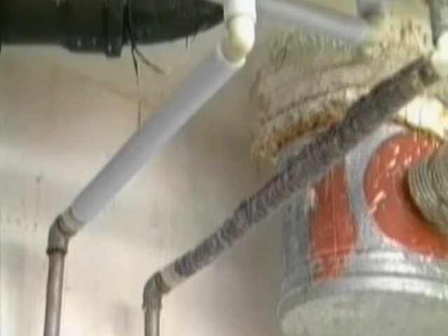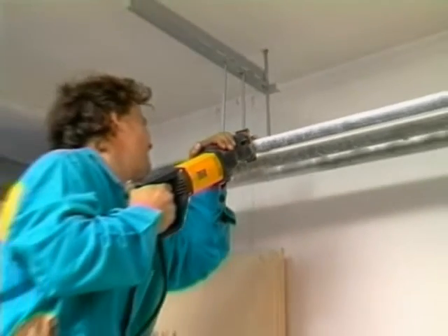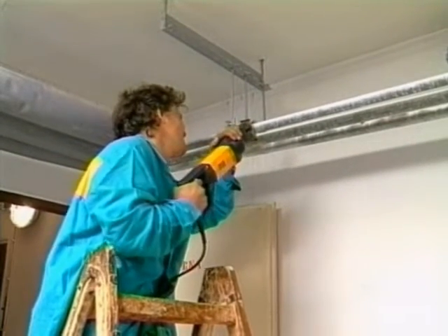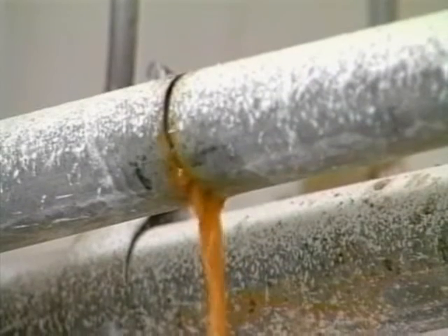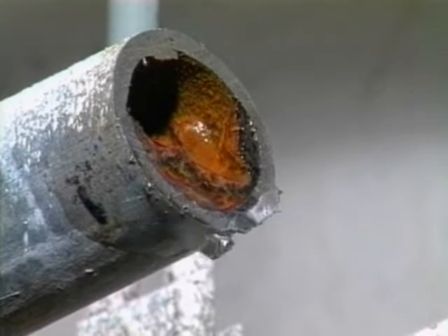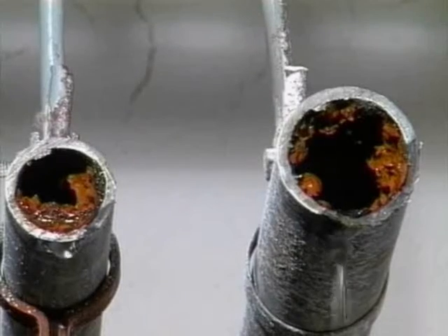During reconstruction, it is usual to gradually replace individual riser pipes. One by one, all the riser pipes are replaced and provisionally joined to the existing horizontal pipes. For this temporary connection during construction, adapters with plastic threads are sufficient. After the riser pipes, it is necessary to change the horizontal pipes. Again, of course, we start with dismantling the existing plumbing, which, just as the galvanized steel piping, is suffering from incrustation and even more corrosion.